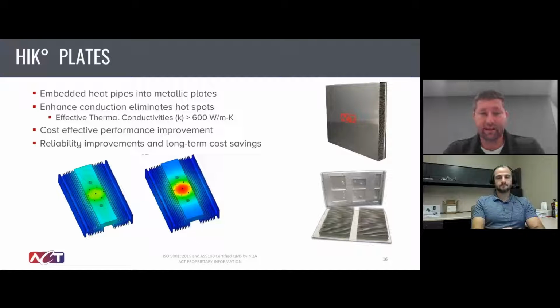And then on the right side, 2 examples of fielded hardware for this exact scenario. So these were both IGBT cooling applications. The top one was a naval power electronics cabinet, and that one had multiple IGBTs mounted to the backside of what you're seeing here. And it's a little hard to tell, but the fins that you see there are very tight pitched. So this one actually had a high airflow going through those fins, so we're allowed to get a lot of surface area and space those fins out very, very tightly across that.